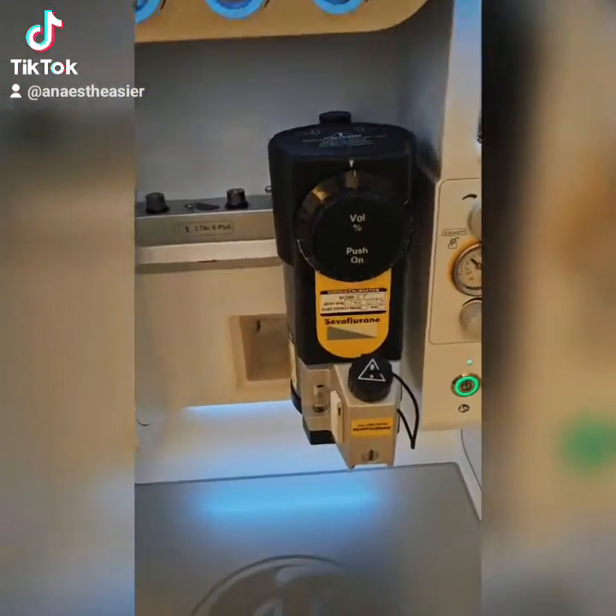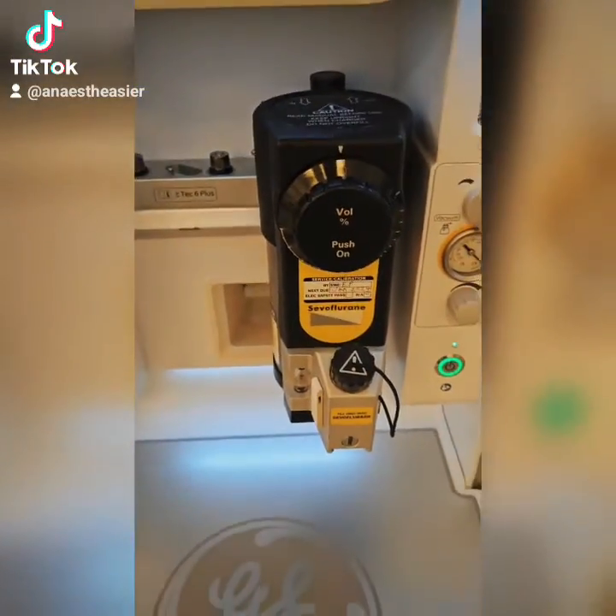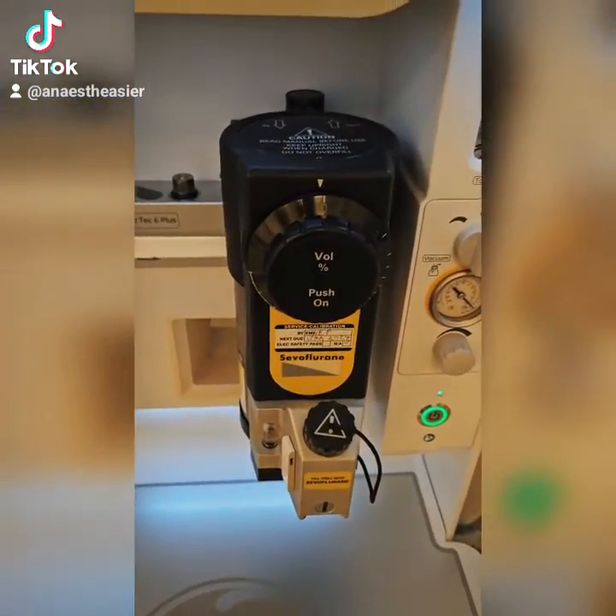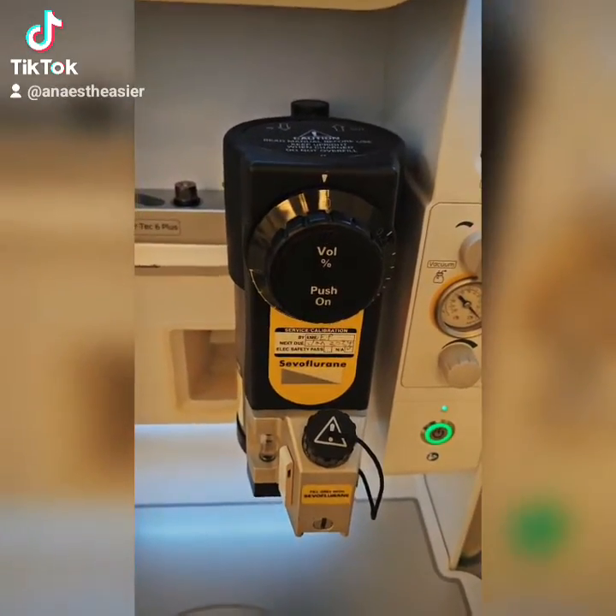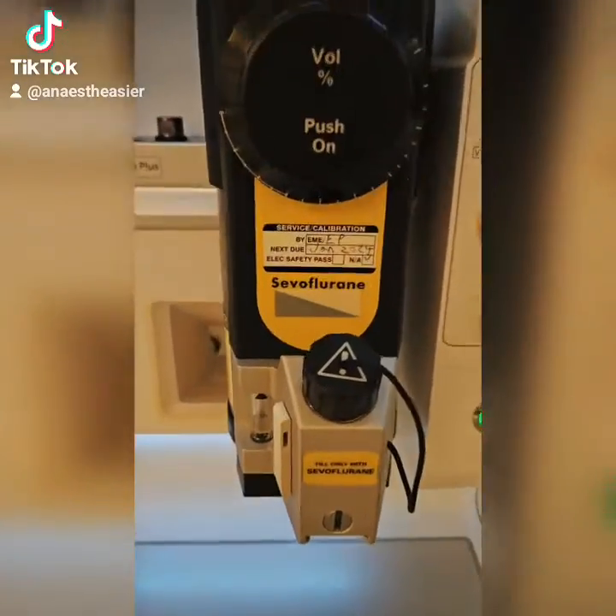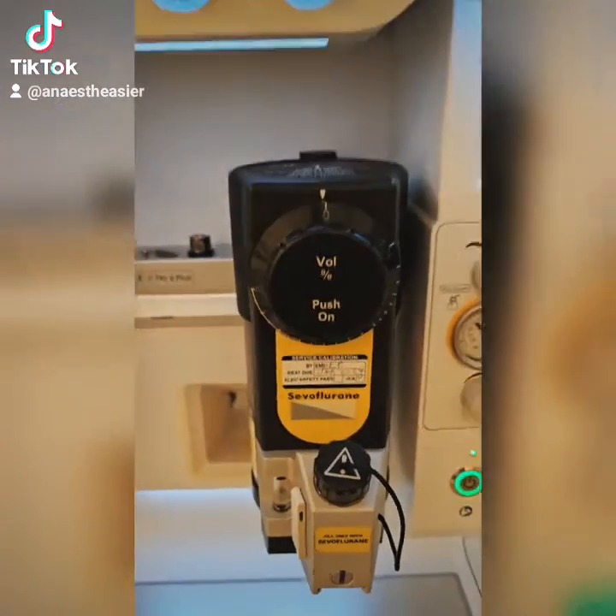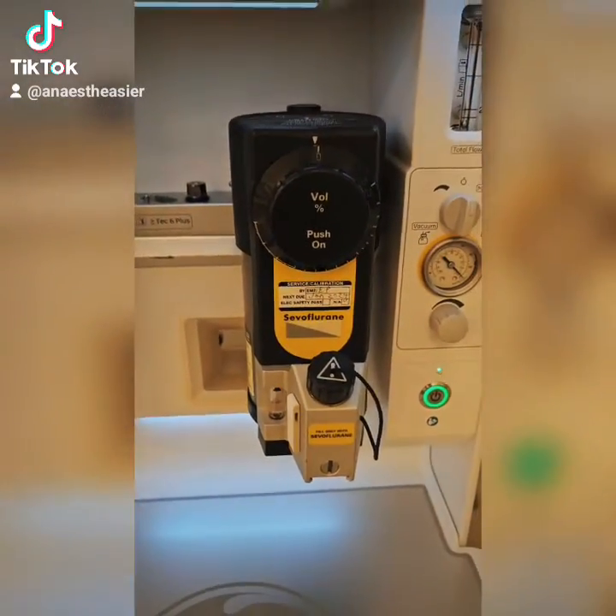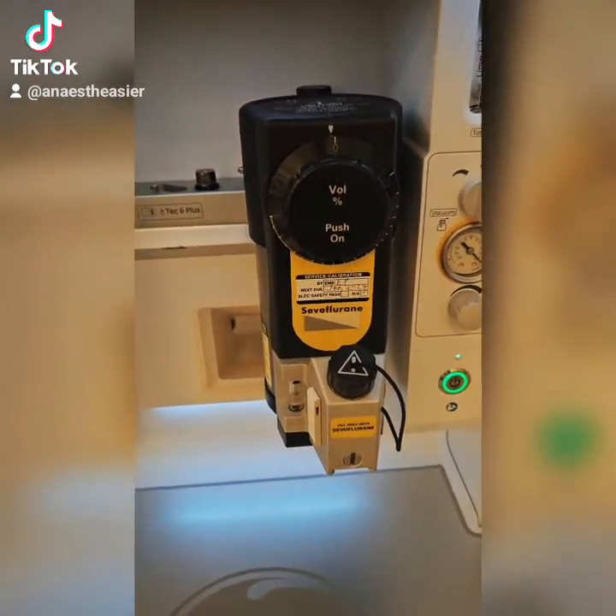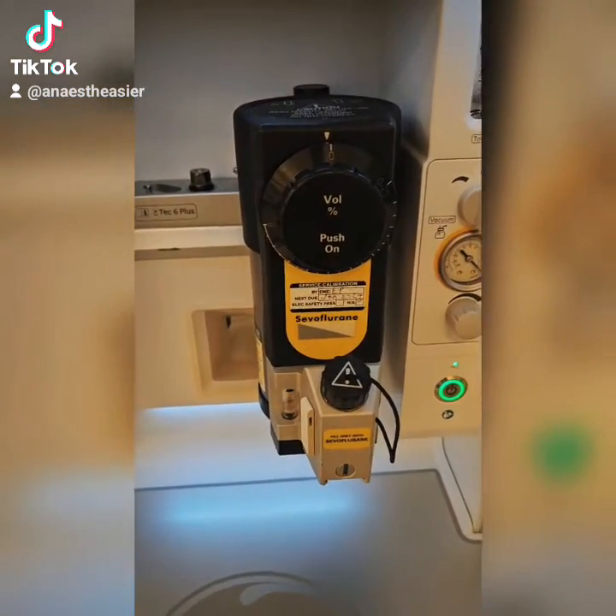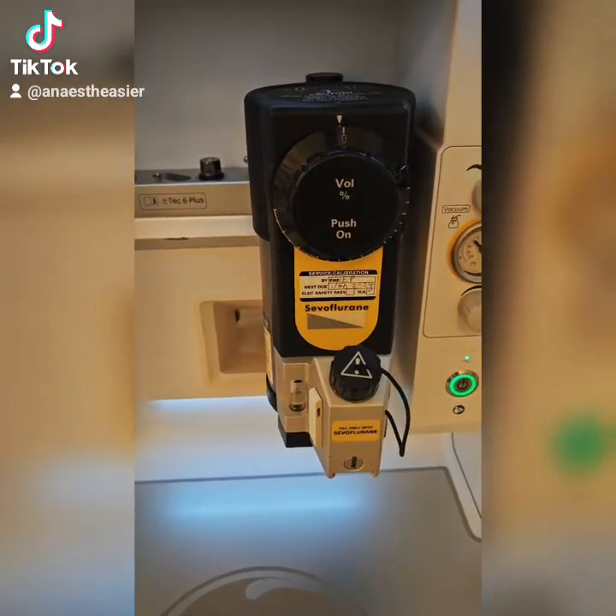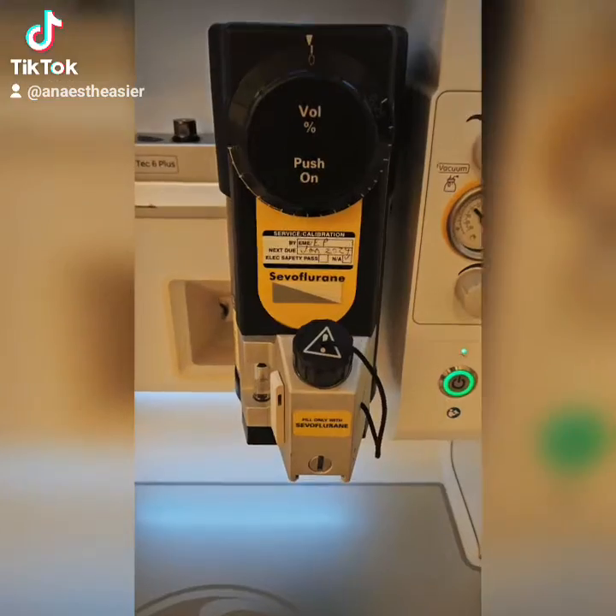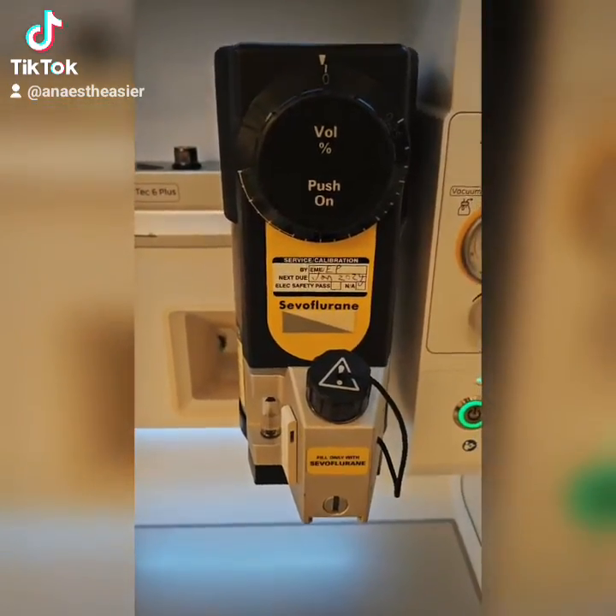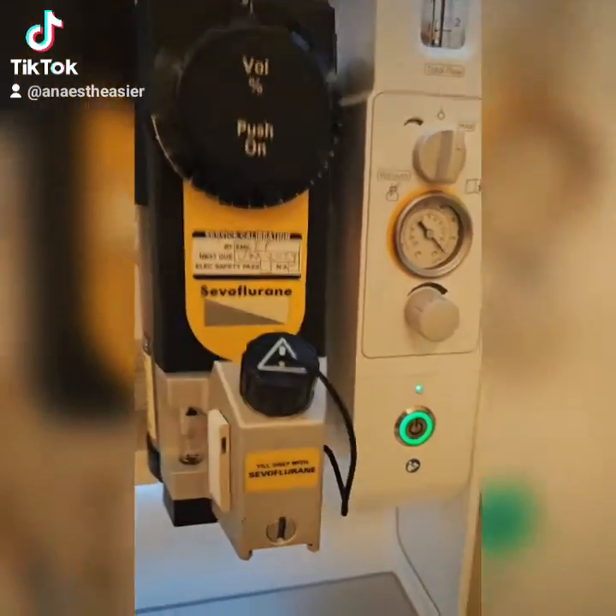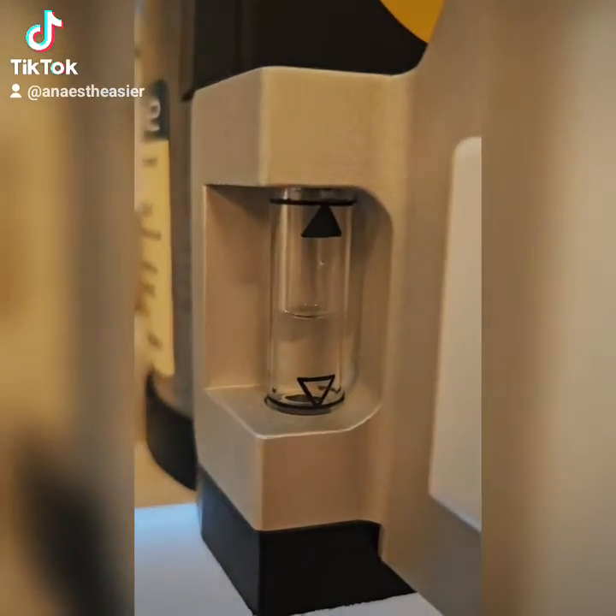The most important part of the machine is probably the vaporizer. This device is a really clever piece of kit, and what it does is essentially has liquid. So this one's a sevoflurane vaporizer, and every vaporizer is specific to the agent that it gives, because the volatility of each vapor is completely different. So they have to have different vaporizers. So a sevoflurane vaporizer will only work with sevoflurane. The liquid is put in the front here. You can see there's a dial like in your car, tells you how much you've got left.